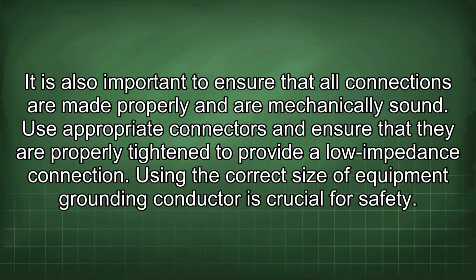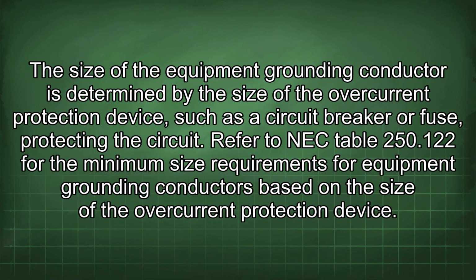It is also important to ensure that all connections are made properly and are mechanically sound. Use appropriate connectors and ensure that they are properly tightened to provide a low impedance connection. Using the correct size of equipment grounding conductor is crucial for safety. The size of the equipment grounding conductor is determined by the size of the overcurrent protection device, such as a circuit breaker or fuse, protecting the circuit.